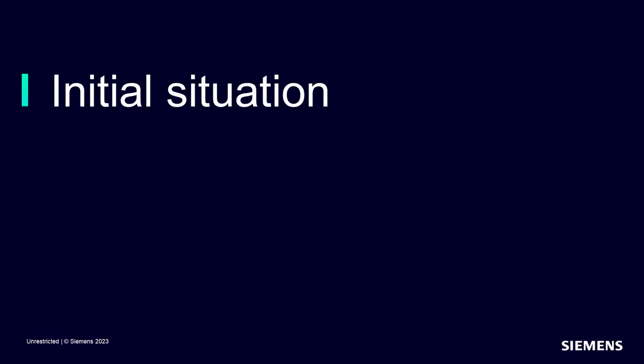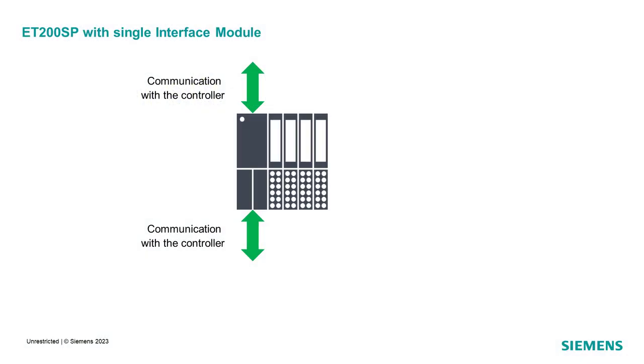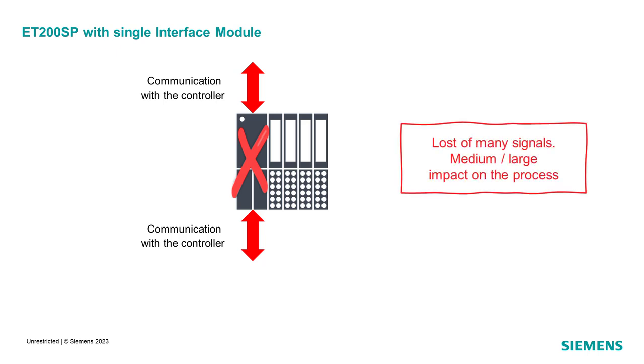The standard setup of an ET200SP station is based on a single interface and I/O modules. This interface is used for the PROFINET communication with the S7 controller. In case of interface module failure, the communication is interrupted and many I/O signals are lost.